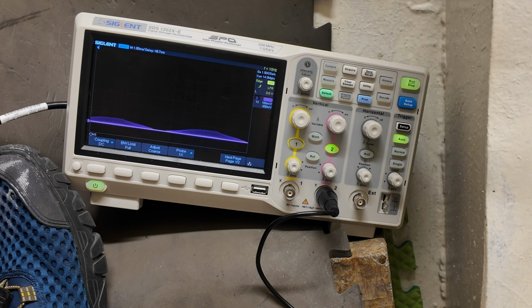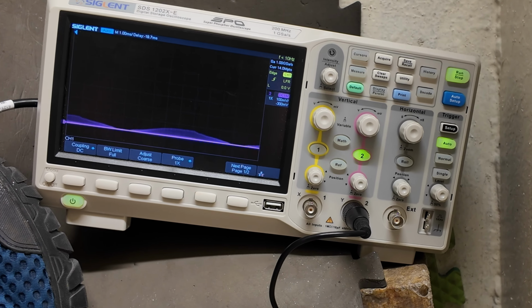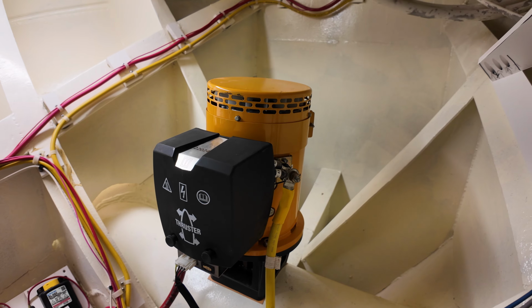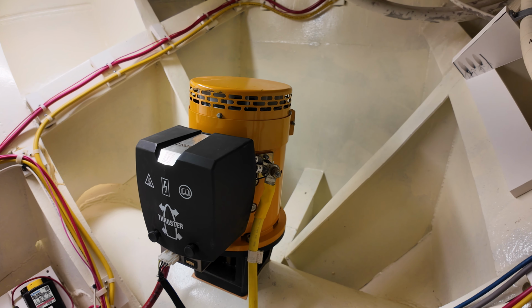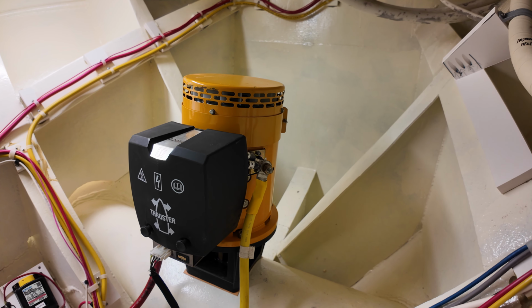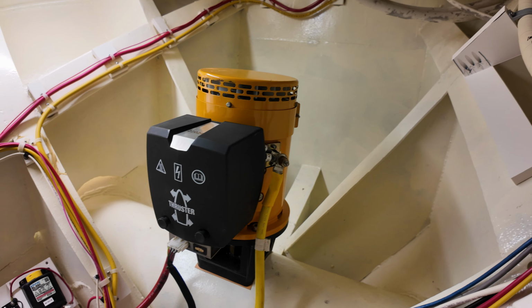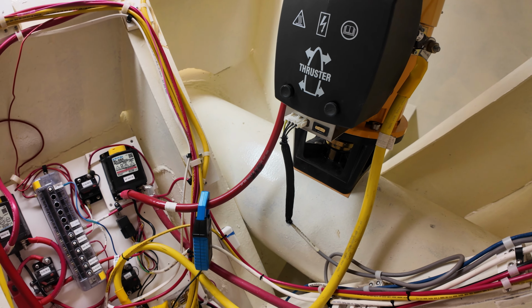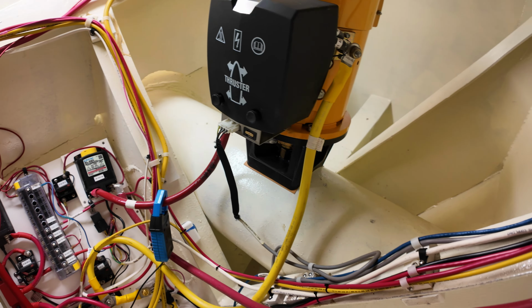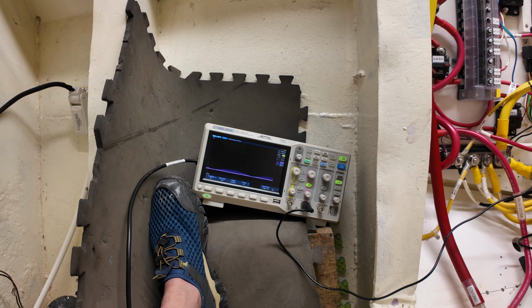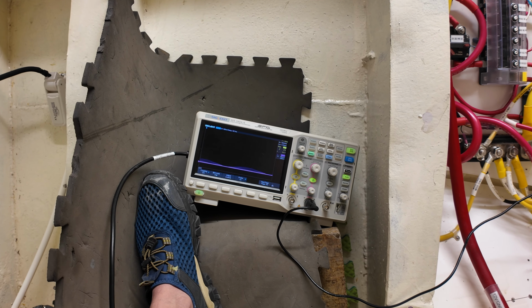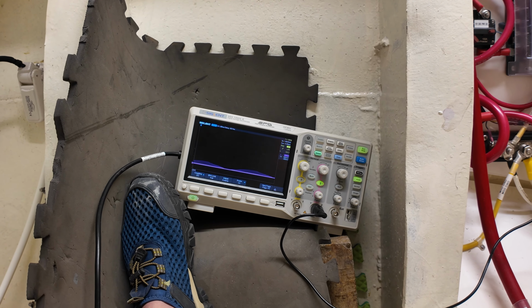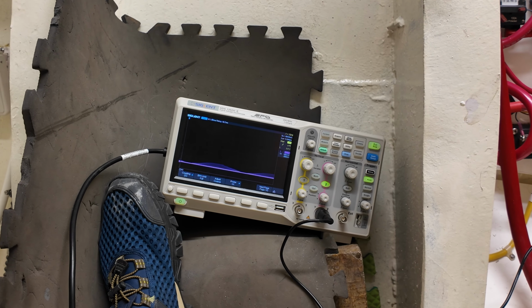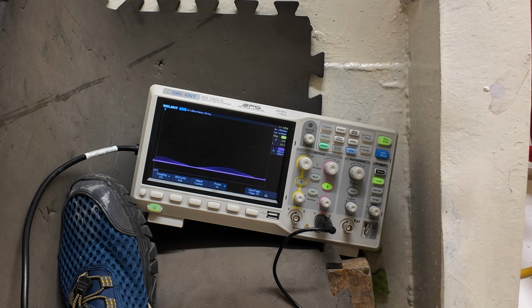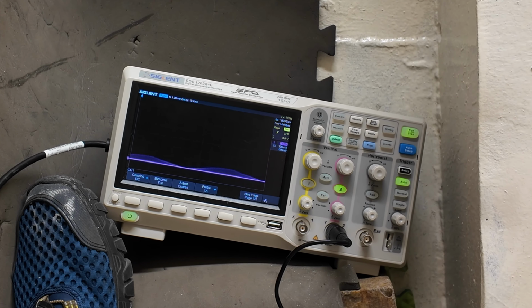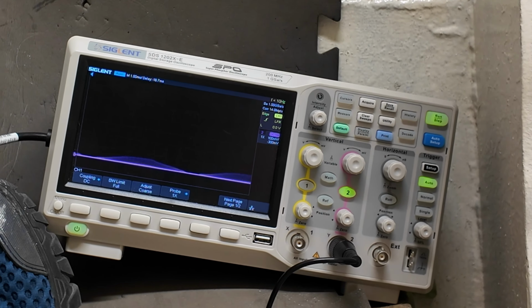The first reading we're going to do is how much current the bow thruster uses. We'll do a couple samples - right now I've got the meter on the red line, then switched over to the black line. I may switch it earlier because I'm not sure which direction the waveform will go on the oscilloscope, so that may be reading negative current right now. About 600 amps is what I can currently see on that screen. That's what we're going to start testing with initially.